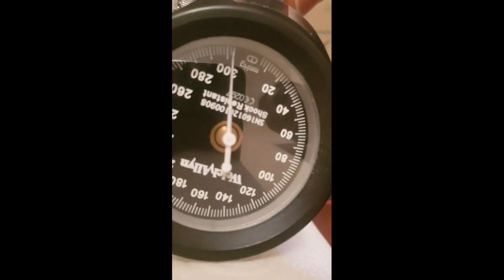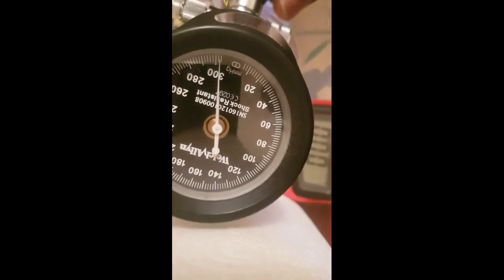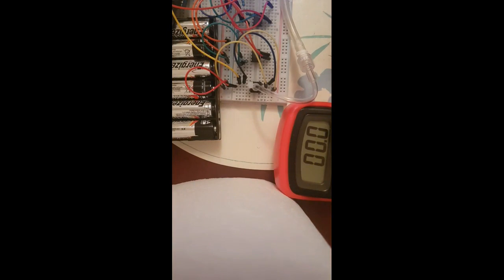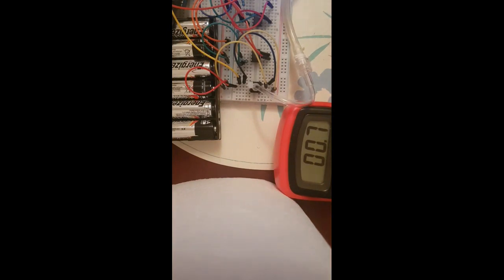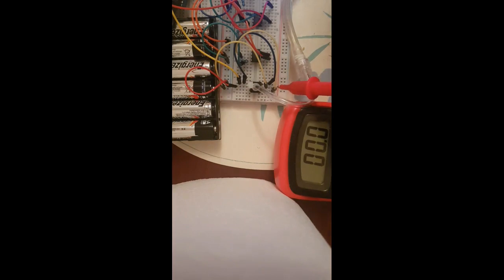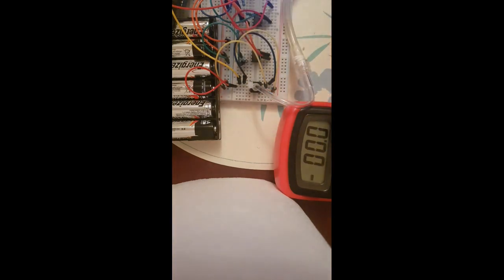Now as you can see on the manometer I have increased the pressure to 300 mmHg which is the sensor's maximum pressure it can measure. I'm now going to measure the output voltage we get from this pressure. And we get 75 millivolts which is in between the range that was specified on the datasheet. If you remember the range was between 50 and 100 millivolts.